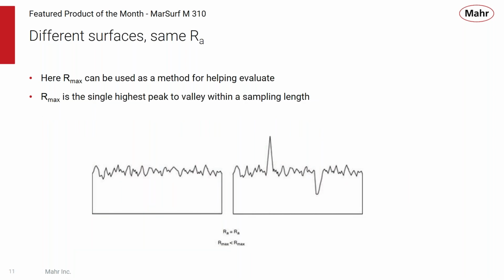There's another pretty simple one where, if it wasn't for the peaks and the valleys on the surface on the right, these would have very similar roughness averages. So in this case, you might want to look at an R sub max value, which would help calculate and find those peaks within the surface. And a peak in this case might be a source of scratching or marring the part that it mates to. Or it could be, if you're trying to coat this part, that peak may pass through and not be coated by the coating. So different parameters for different characteristics.